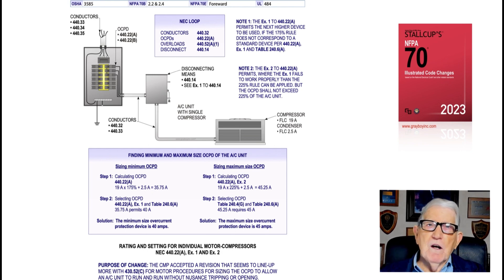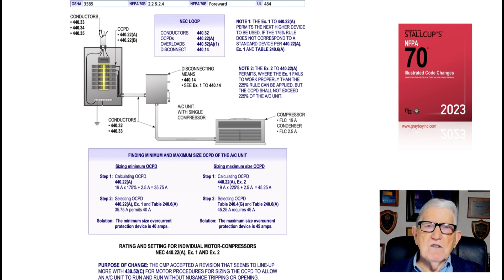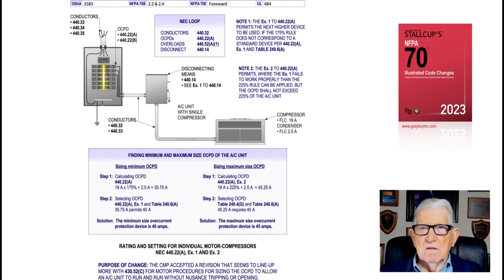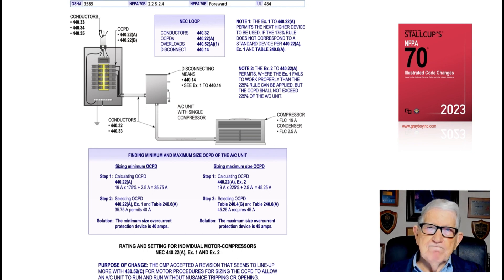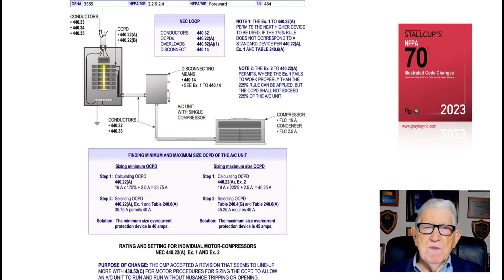This section 440.22(A) parallels what you're doing in 430.52(C)(1). The NEC loop gives you the sections for conductors, overcurrent devices, overloads, and the disconnect — which are mainly the key sections you look at to design a branch circuit with a disconnecting means to the AC unit. That's all this illustration is showing the user: when to round up and when to round down based on the 175% rule or the 225% rule.